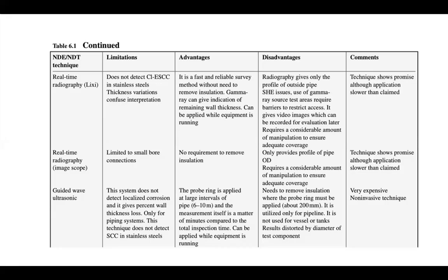And what about real-time radiography with image scope? Limited to small bore connection. Advantages: no requirement to remove insulation. Similar to the real-time radiography, LIXI. And disadvantages: only provides profile of the OD, outside diameter.